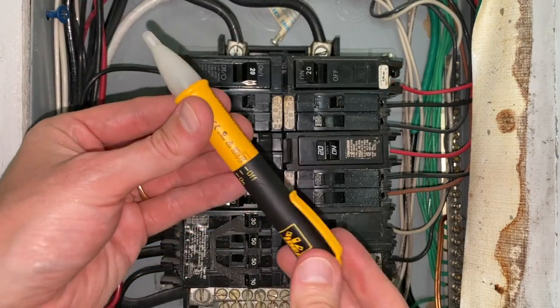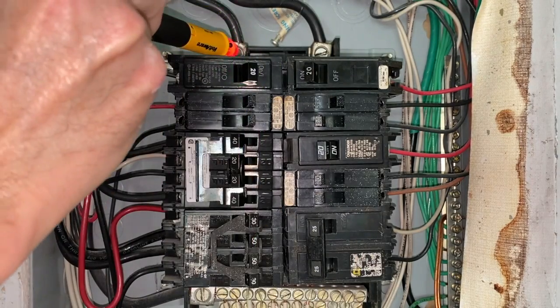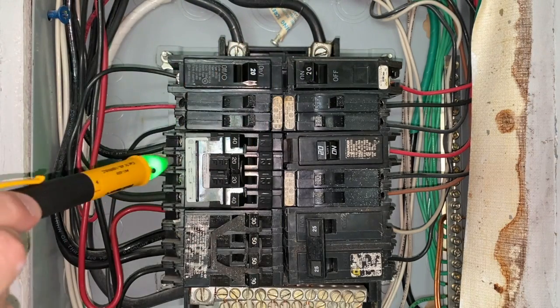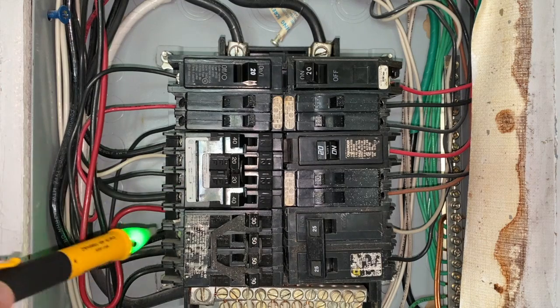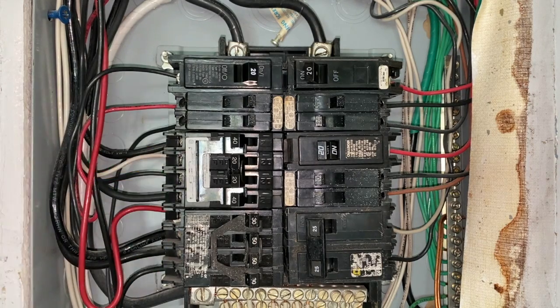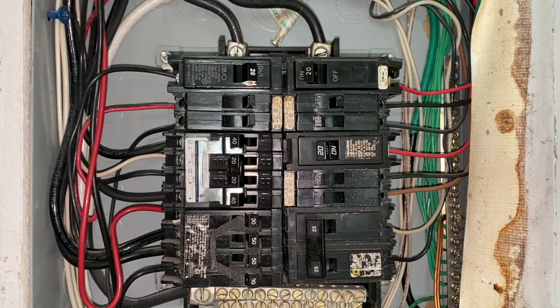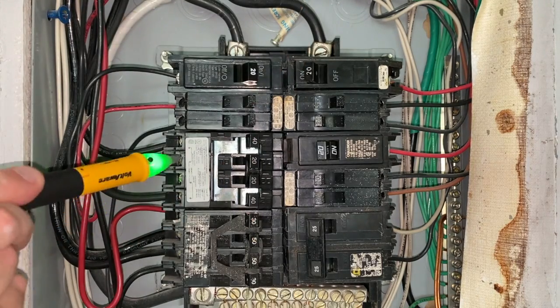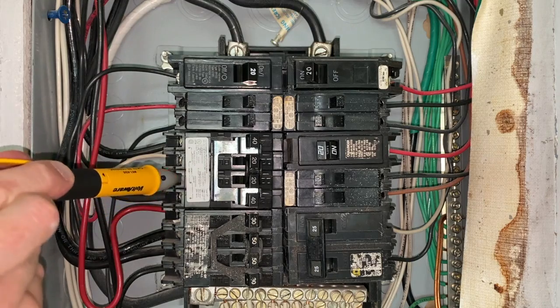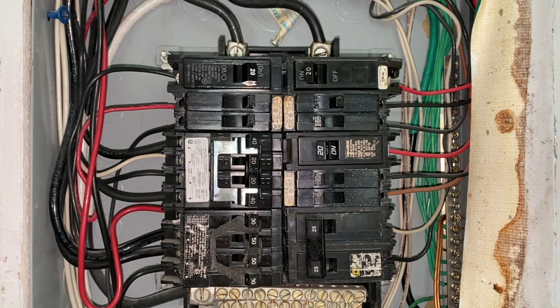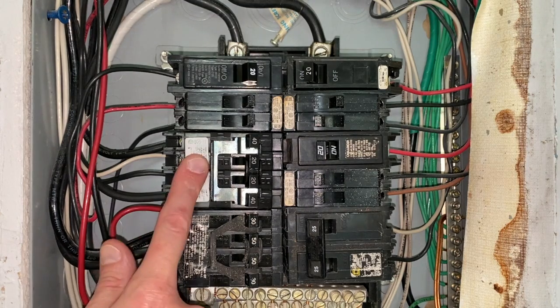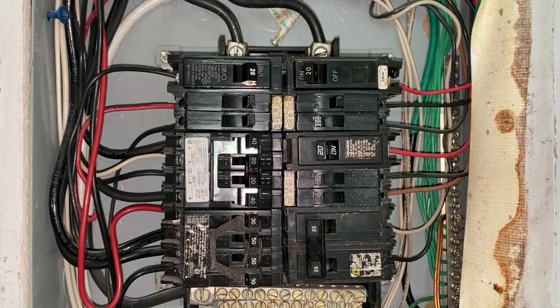Back inside and grabbing this tool and turning it on, as shown there, and detecting electricity will blink and beep red as you see. And again, these are off and these are on. And I'm going to turn the 4-pole breaker back on and ensure it's working properly. I hear the hot water up and running now. And again, over the next couple hours, I'm just going to monitor this to ensure it's not overheating or humming, or the absolute worst, giving off burning odors, which would be an extremely unsafe situation.